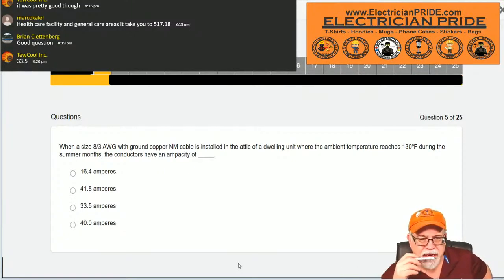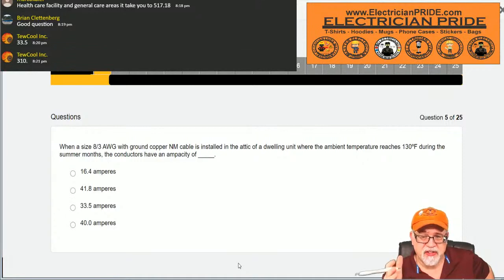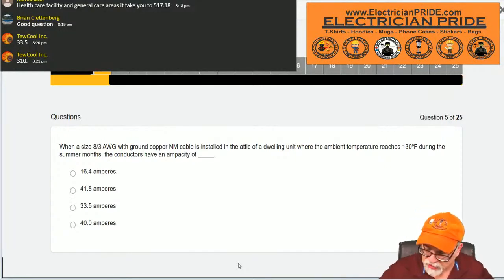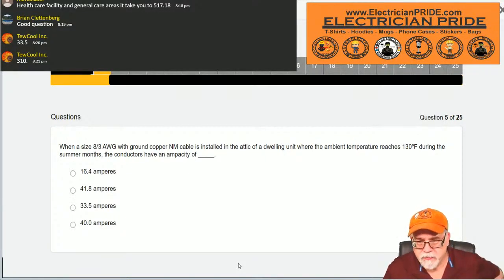And a couple things that I will remind you: NMB is rated 60 degrees, okay? But you can use the 90 for adjustment and corrections as long as you don't exceed the value of the 60-degree column, so you still have your terminal limitations you got to be aware of. All right, so all those goodies to be aware of. So the first thing that I would do in this question, and hopefully we get some more answers up there. Oh, the code reference, thank you, Too Cool. Appreciate it.